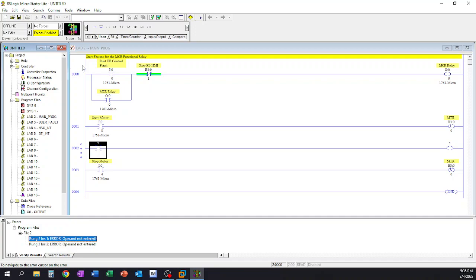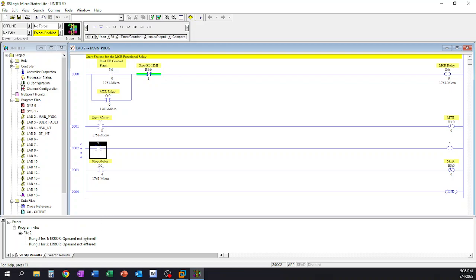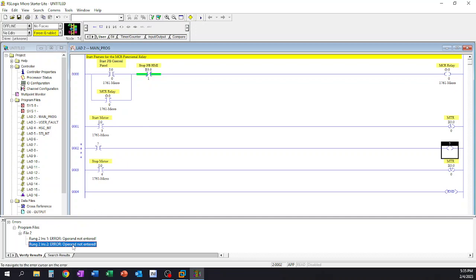It's going to tell us, so we scroll down and find rung 2 and we see that we have an error and it says operand not entered. So instance number 1 is going to be this here and what it's saying is the operand is not entered, so there is no location where this is going to. So we have a function but no operand for it to send the function to or to receive the function from, so it doesn't understand what you're doing there. It's like a syntax error. And then the second thing, instance number 2 on rung 2, same thing over here.